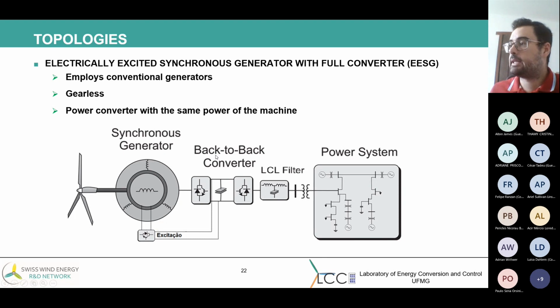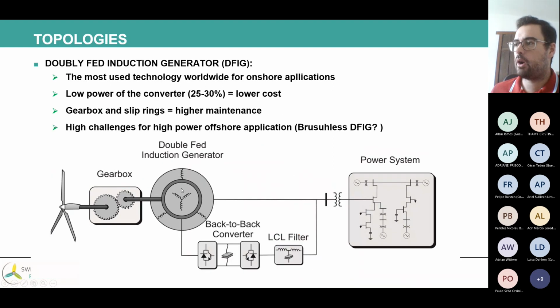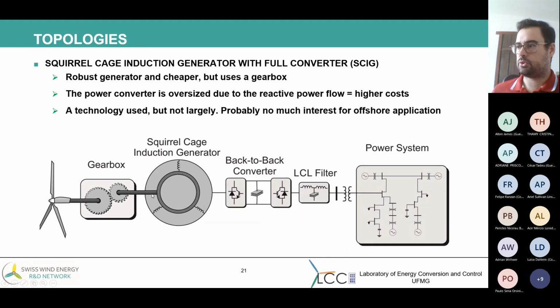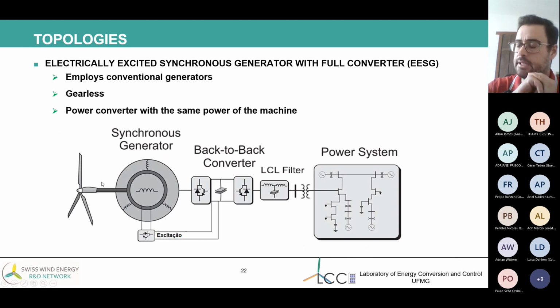The power converter has the same power as the machine. If you have a synchronous machine with 10 megawatts, the converter is of 10 megawatts. This technology is cheaper than the SCIG, but more expensive than the doubly fed. The advantage of the synchronous generator is the absence of the gearbox, so less maintenance. But the electrically excited one also has the problem of brushes and slip rings, which can be avoided in some technologies. And so it's a technology very used in onshore applications.